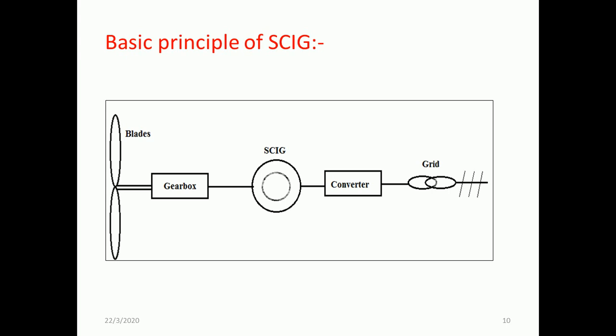A squirrel cage induction generator is used, and further a converter is used because generation may be in AC, transmission losses are to be reduced, and thus a DC system has to be employed. So this is a general topology which can be used in any type of generator. This is the general topology for a squirrel cage induction generator.